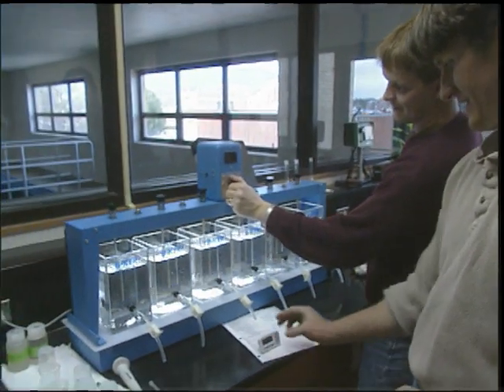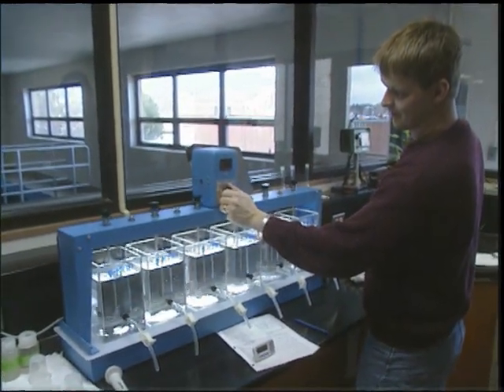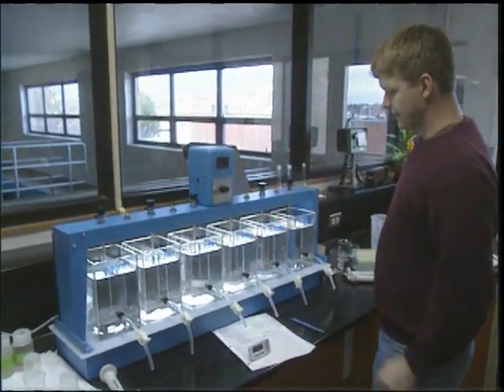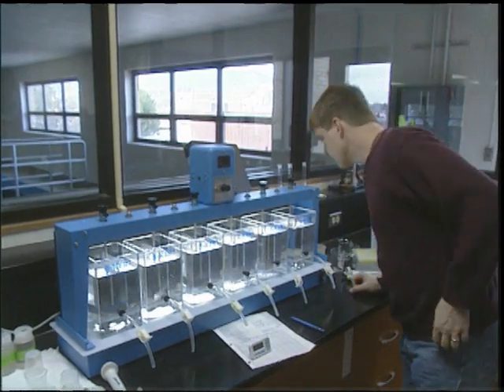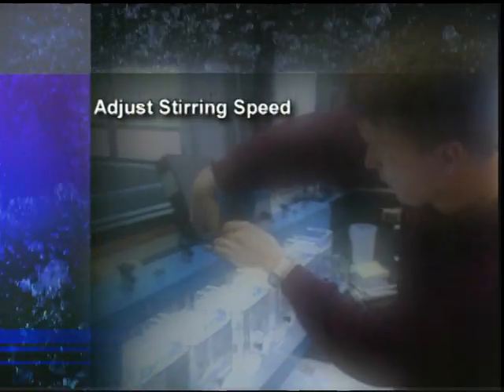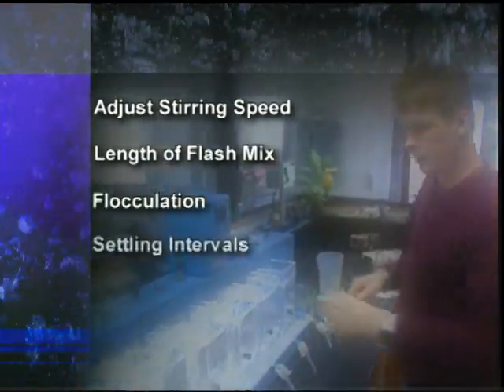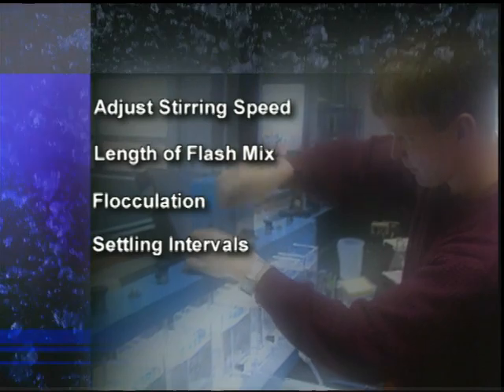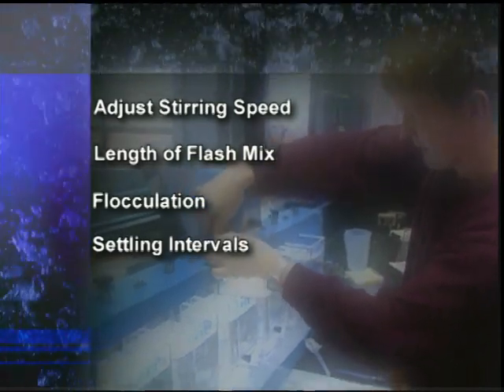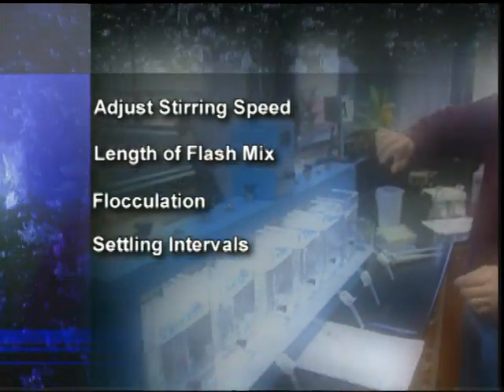Perform several calibration jar tests to ensure that the results will mirror the performance of the full-scale chemical treatment used in the plant. Adjust the stirring speed, length of the flash mix, flocculation, and settling intervals until the jar test conditions closely match those used in the full-scale plant.